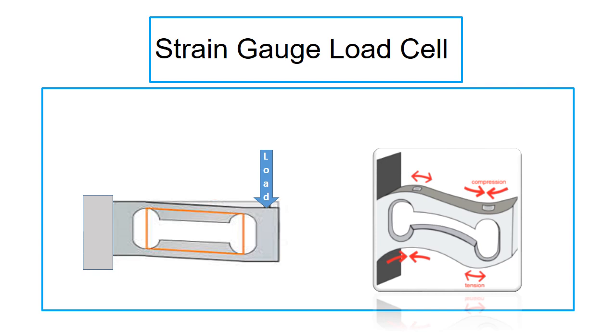In response to the body shape changes, the strain gauge also changes its shape. This causes a change in the electrical resistance of the strain gauge, which can be measured as a voltage change. This change in output is proportional to the amount of load applied.